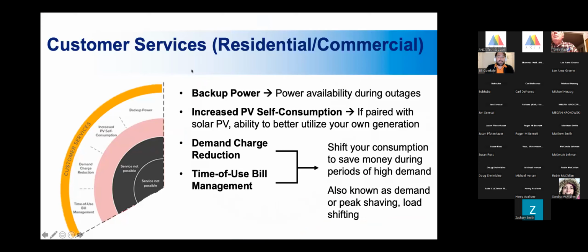Primary uses for customer services are backup power. If you have just solar without a battery and the power goes down, you are not going to have power, because your inverter will sense the outage and shut off production. With energy storage paired to that solar, you will be able to have power in most cases during a broader power outage, because energy storage technology can provide the capability to island from the grid.